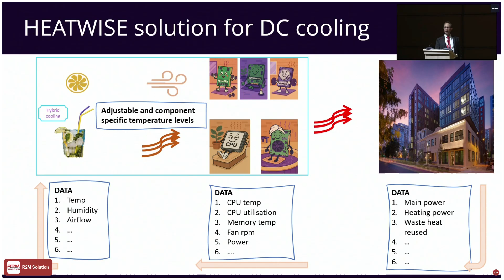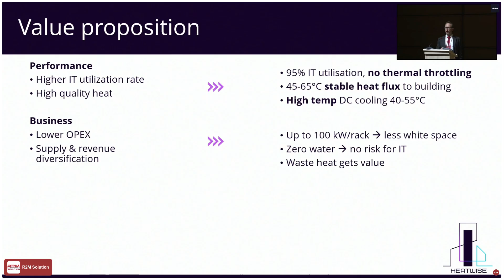If we implement this solution, we have a pretty impressive proposal. Based on our research, we believe we can achieve 95% IT utilization, a stable and on-demand temperature, even reaching 65 degrees liquid to liquid, which also means impressive business advantages in CapEx and OpEx. We believe we can achieve lower CapEx, lower OpEx, and overall less TCO, and fit around 100 kilowatts of IT in one rack—compared to the current 5, 8, or 12 kilowatts. So it's a big jump.